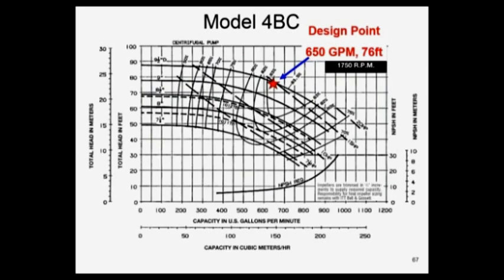We need a flow rate of 650 reading straight down to the bottom horizontal, you see the flow rate is GPM on the bottom. Vertically you'll see it in meters and in feet of head. In this case we're looking for 76 feet of head going off to the vertical axis.